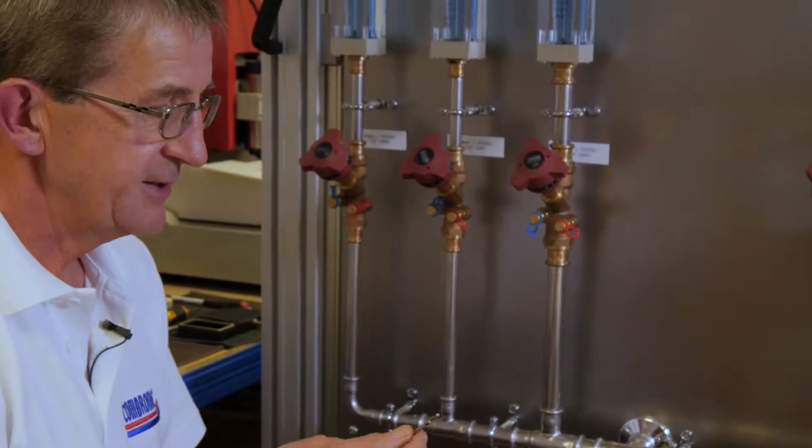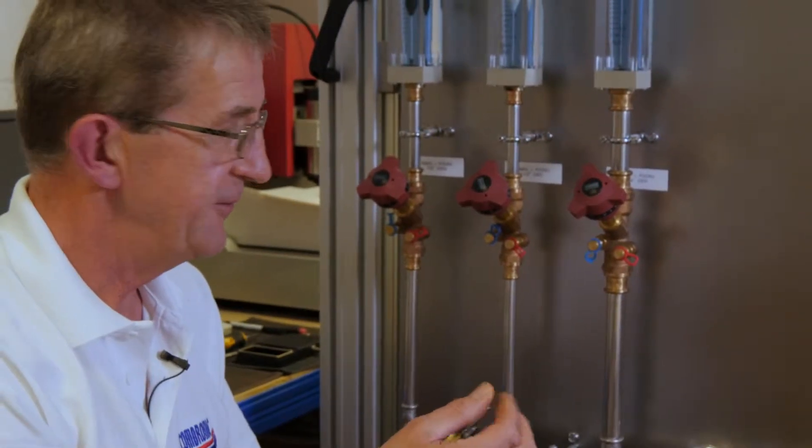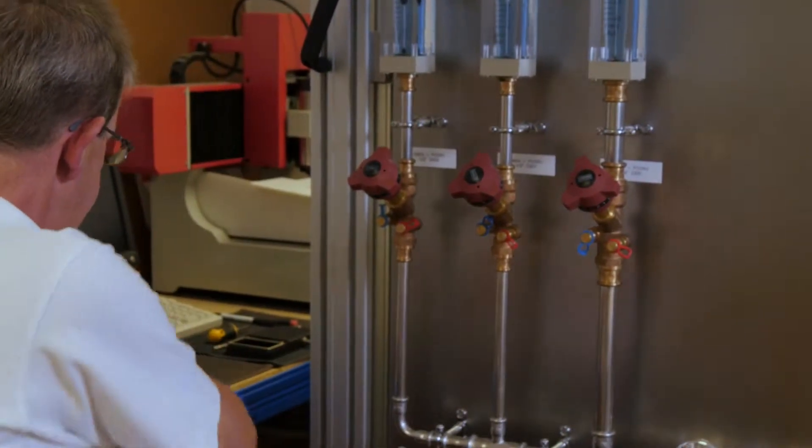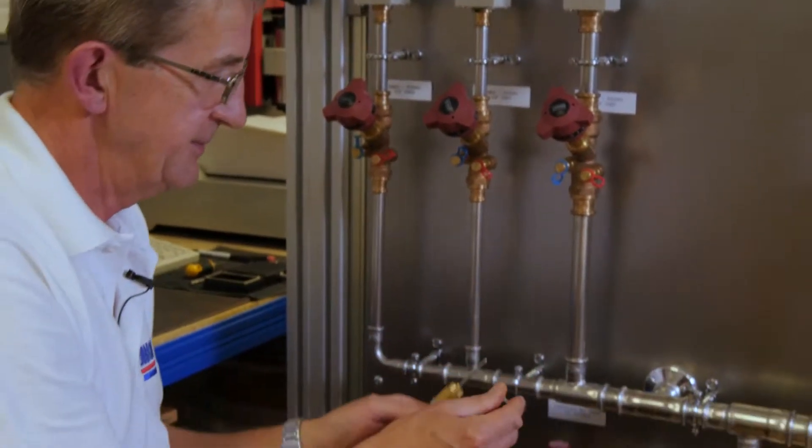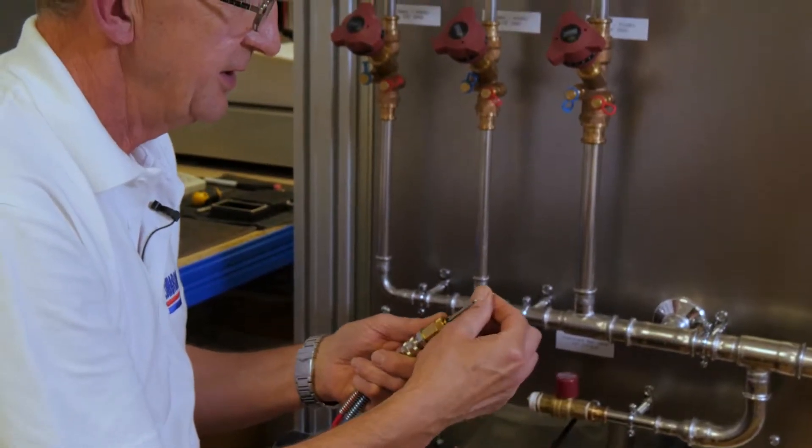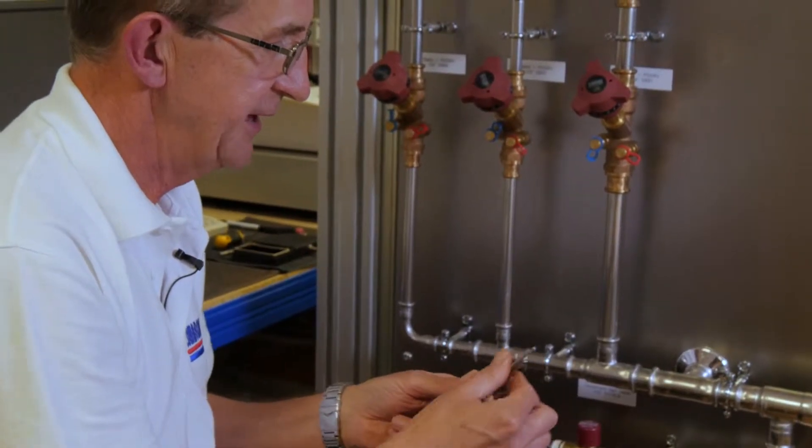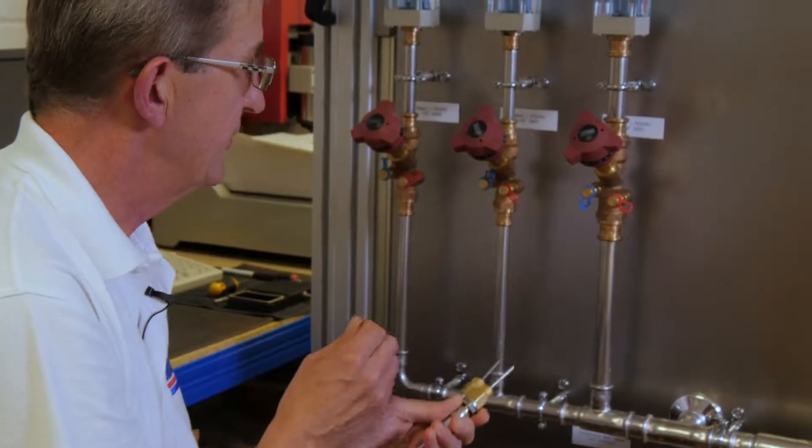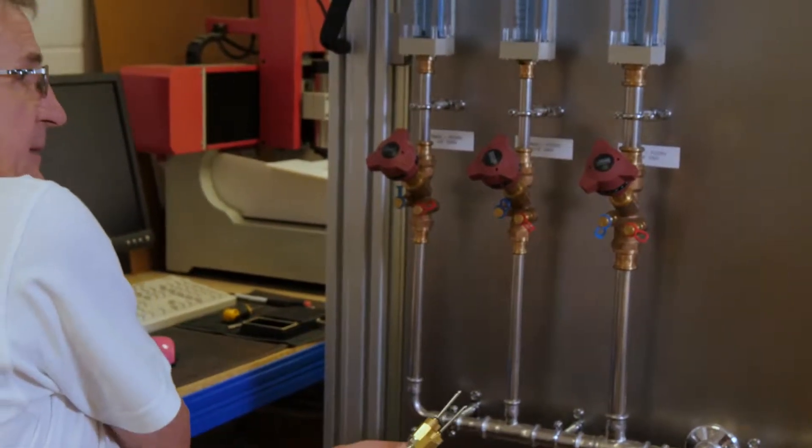The first instruction is connect the red and the blue hoses to the balancing valve. Now it's always wise to just lubricate the needles before we try and fit them through the rubbers, and I have some soap solution here which I'm just going to put on the needles just to lubricate the needles to get a nice clean path through the rubbers in the test points.